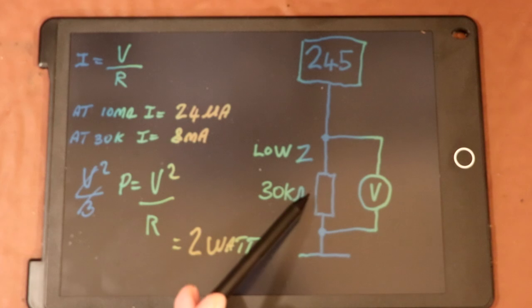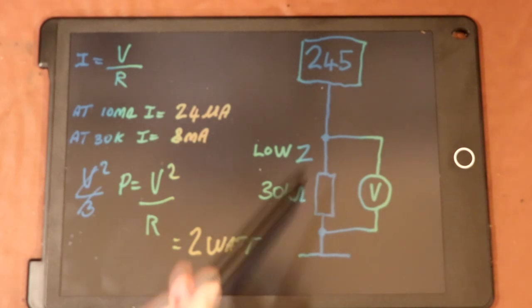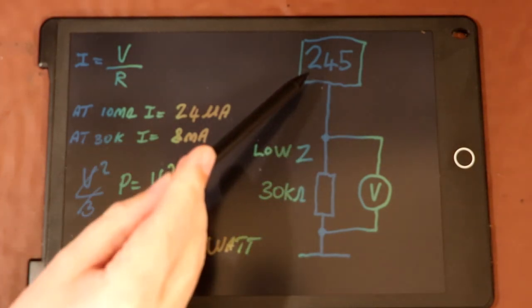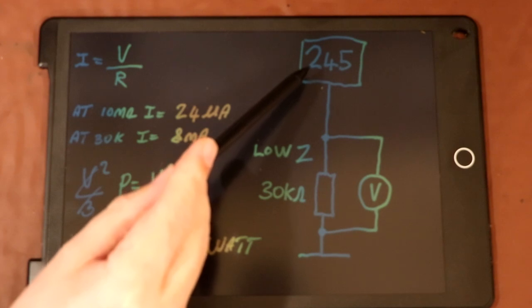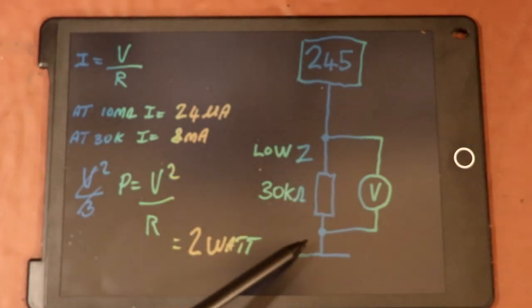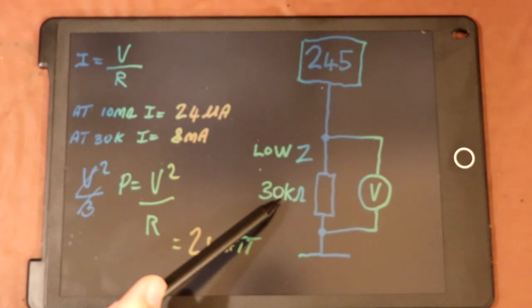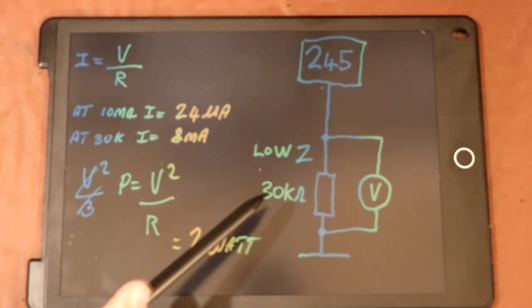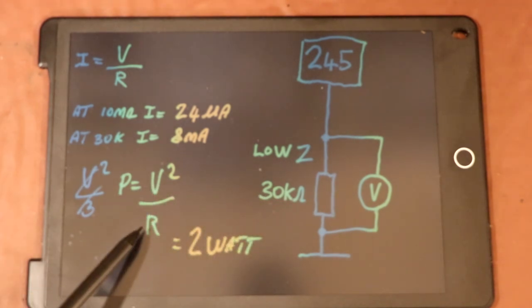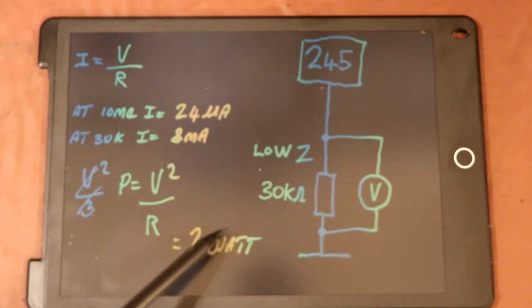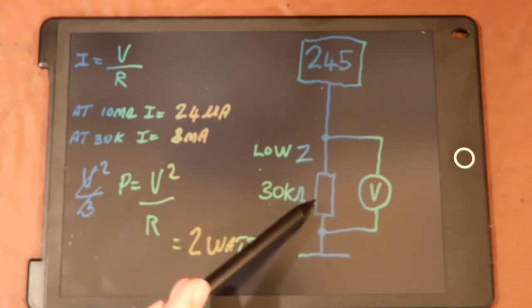Another thing to consider when using the low Z range is whatever your supply voltage happens to be, which in this case is 245 volts, you've got 245 volts across a 30 kiloohm resistor. If you do the maths, which is V squared over R, you can calculate that we've got 2 watts of power being dissipated in that resistor. So this resistor is going to get hot, and for that reason KAIWEETS specify that you can only use the low Z measurement for up to 1 minute maximum.